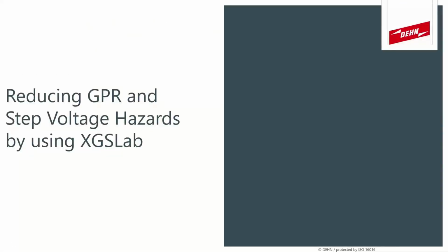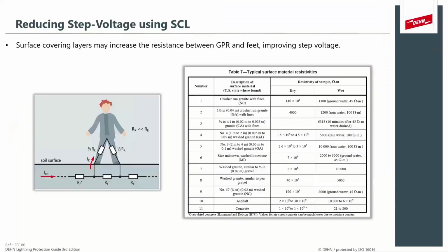The second issue that we need to address is to reduce the ground potential rise and thus reduce the step voltage hazards. We're going to do this again by using the XGSLab software. As I mentioned previously, we can firstly apply a surface covering layer, also known as SCL, between the human body and the ground potential rise, meaning that we will significantly increase the resistance between the two, to ensure there's not a high voltage above that resistance that can cause hazardous step voltages.